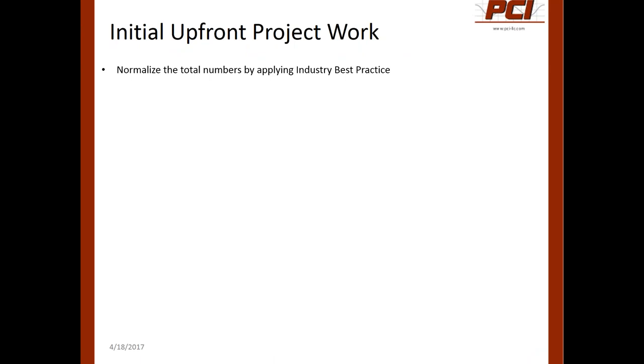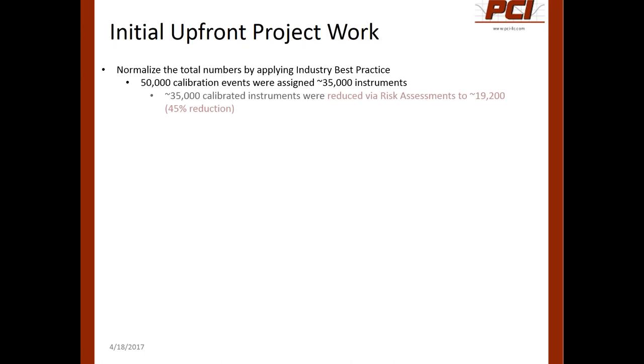We wanted to normalize the total numbers by applying industry best practice first. We knew going into this that we executed a lot of calibrations over the course of a year, and that every site assessed what was critical to them in different ways. So we applied the ISPE baseline guide to calibrations and implemented a risk-based approach. Originally we had roughly 50,000 calibration events assigned to 35,000 instruments. Using a risk-based approach to look at what was truly critical, we were able to reduce those to approximately 19,200 — a roughly 45% reduction.